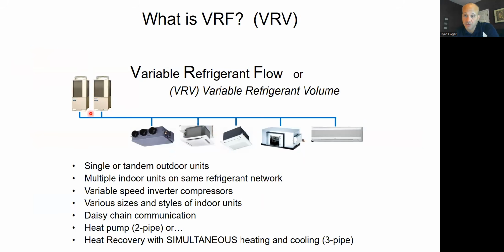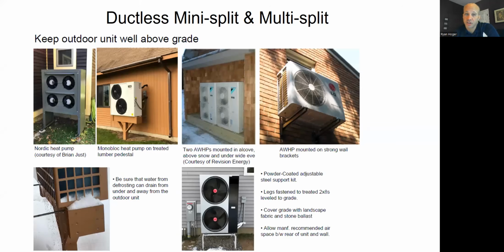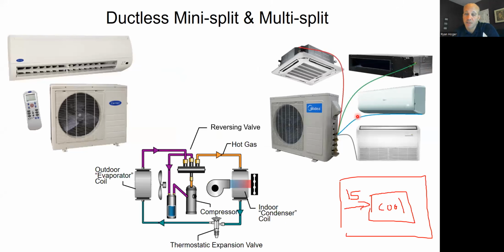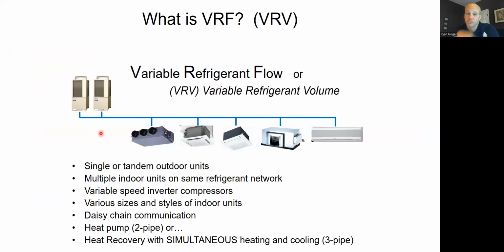Although in this particular example, I have 2 outdoor units twinned together. That's possible, sometimes even 3. But basically, conceptually, I have 1 outdoor unit feeding a bunch of indoor units. The differences between this and that multi-split system that we were talking about. This one is actually going to be 1 piping system that goes down the building, either 2 or 3 pipes that go down the building and then splits off to the individual zones. Whereas the other one, everything was piping home run back to the outdoor unit. So that's a different way of installing it here.